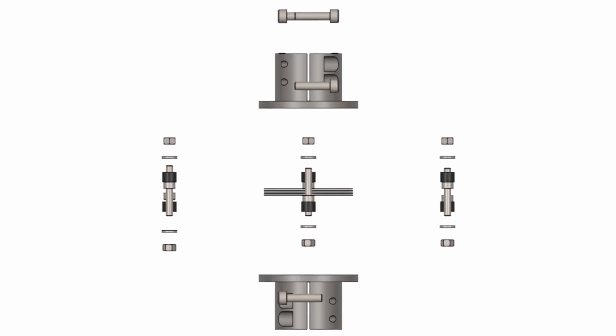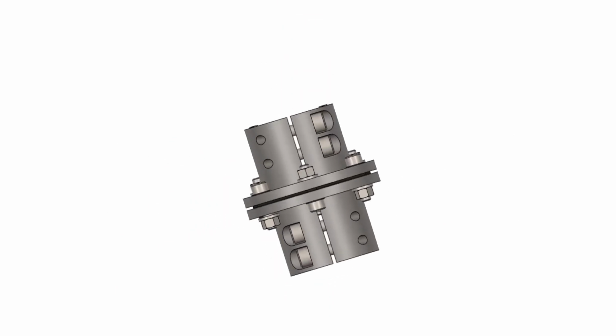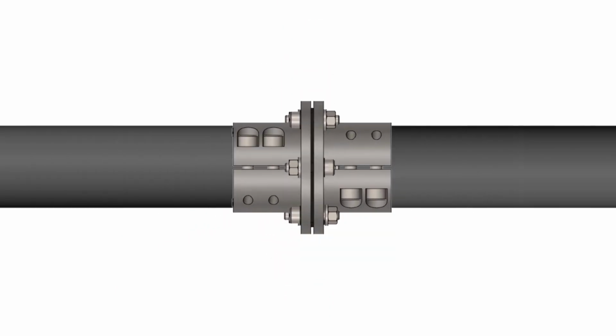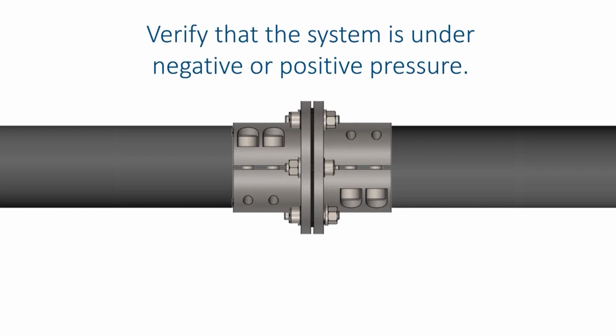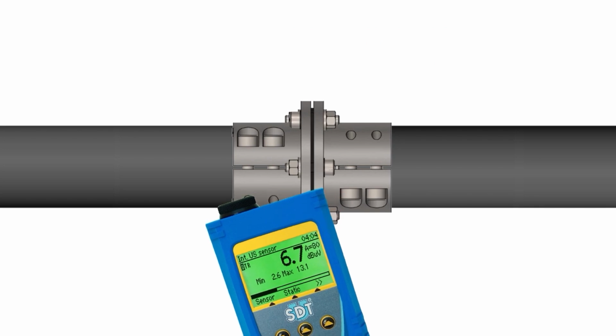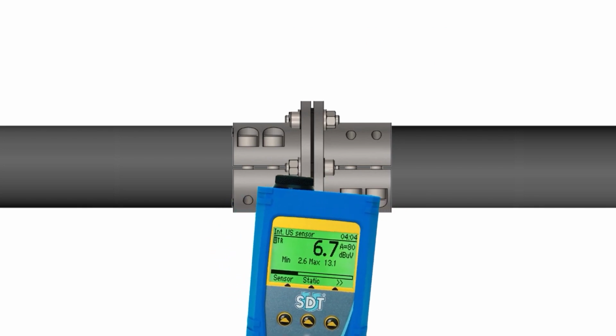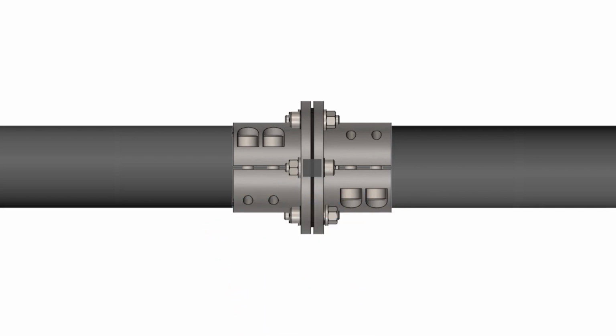Here is a tip for finding a suspected leak in this type of coupled pipe. Here is a typical flanged coupling configuration. First, verify that the system is indeed under negative or positive pressure. Using your ultrasound detector, scan for leaks.